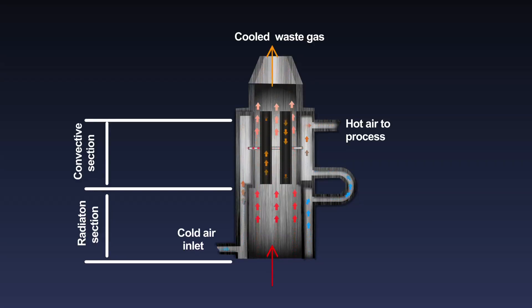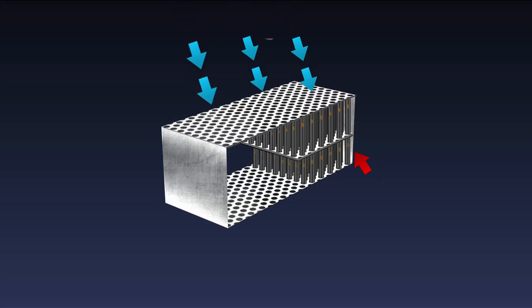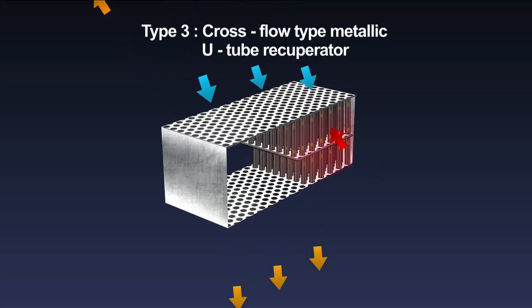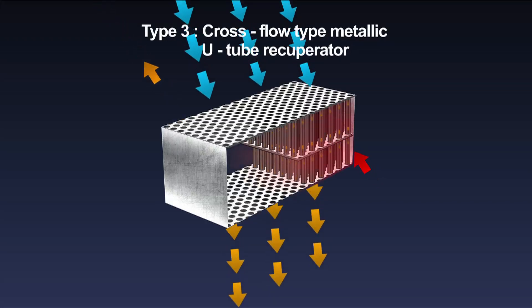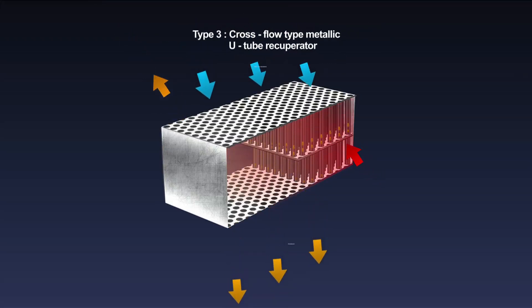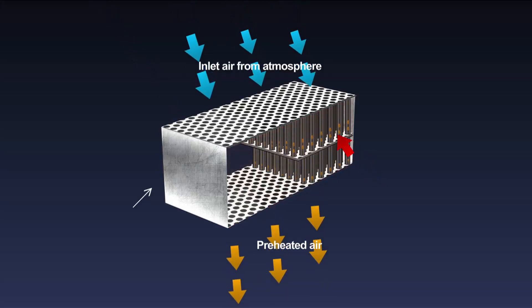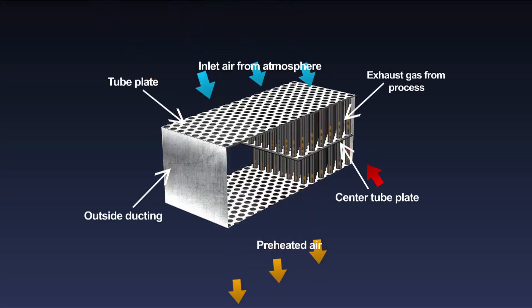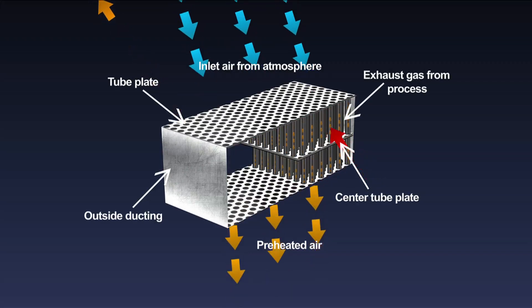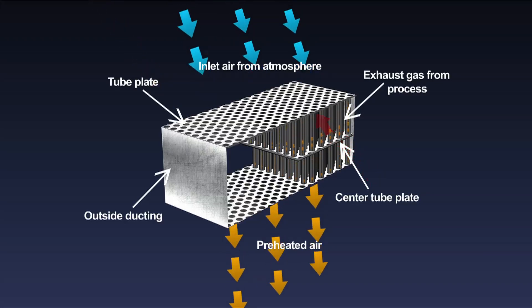The combined design uses a high temperature radiation recuperator followed by a convective design. This type is used in pulverized coal fired furnaces and can recover up to fifty percent of waste heat. The third and most efficient type is the cross-flow type metallic tube recuperator, which can recover up to eighty percent of waste heat. It is suitable for oil and gas fired furnaces and can also be used in pulverized coal fired furnaces with certain design modifications.